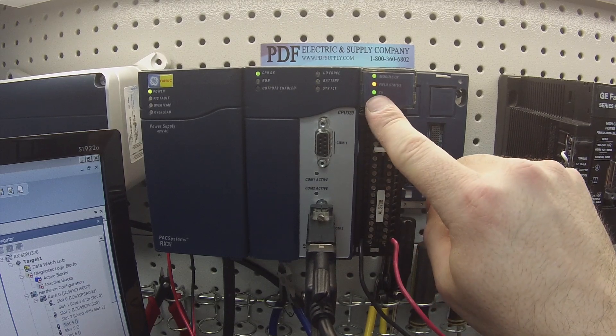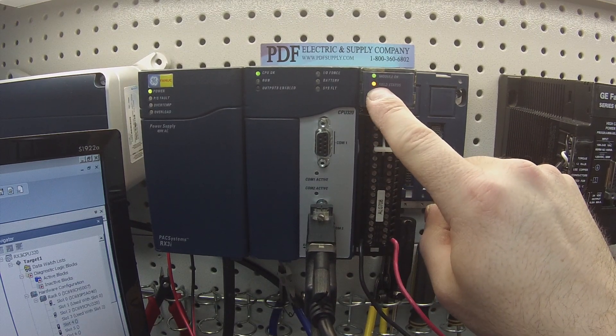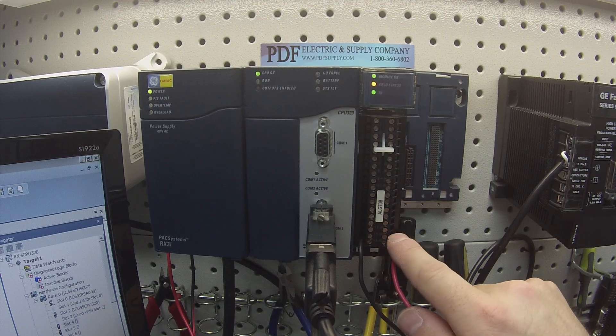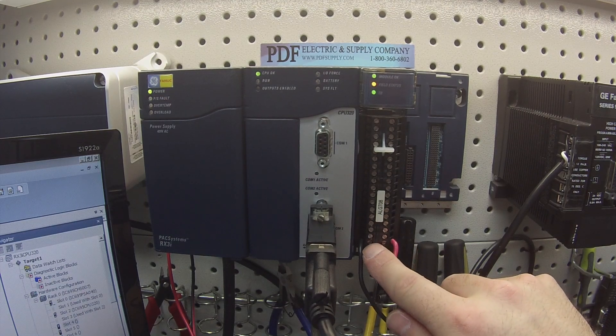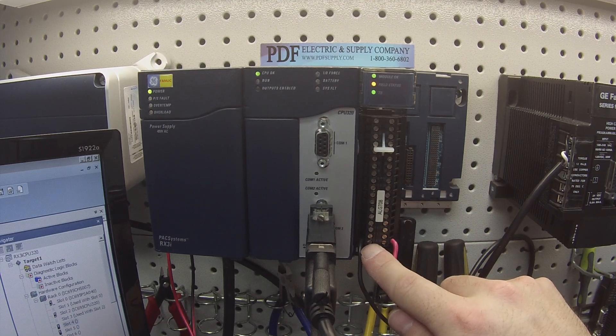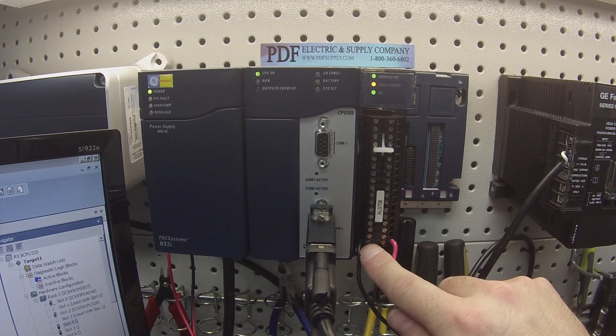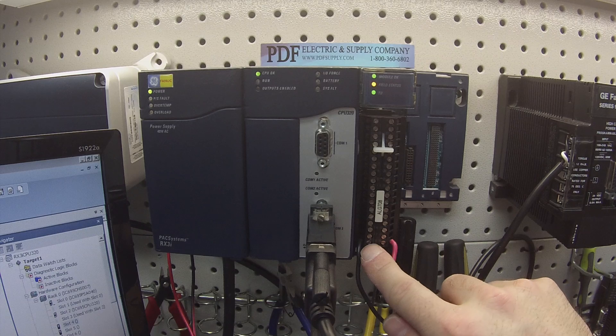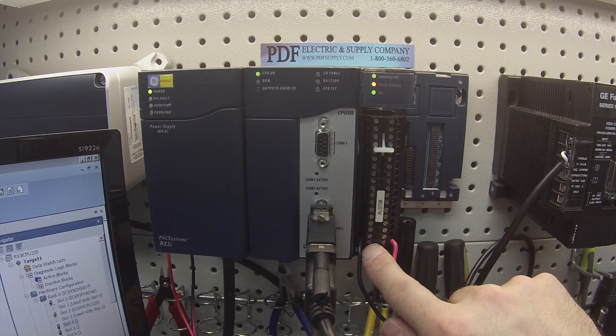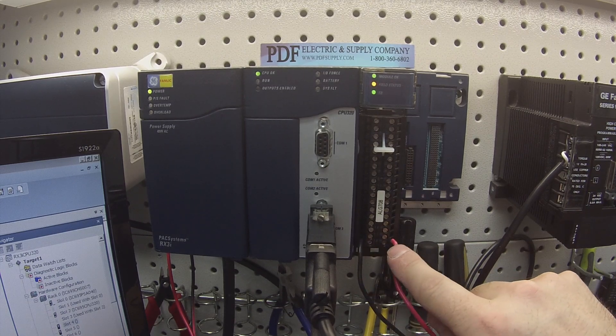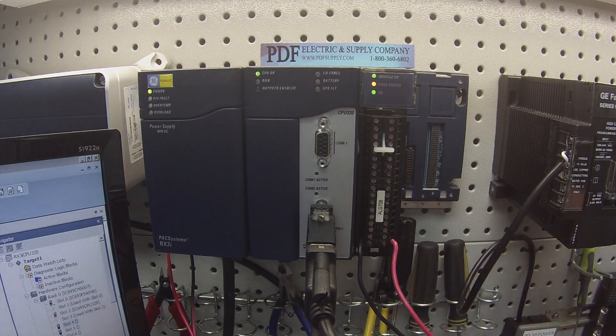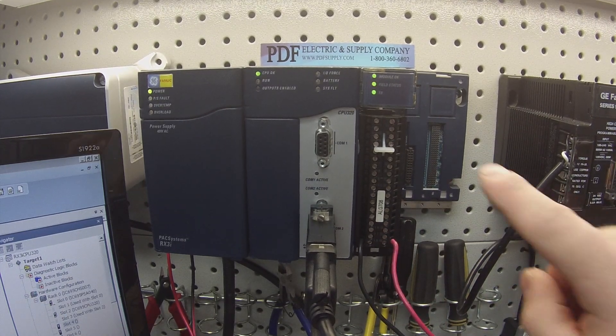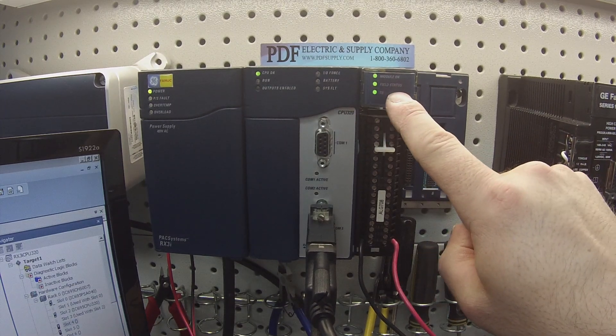It detects that the terminal block is there and our field status is related to these two wires here. This is an output that's going to require power coming in from an external source. I have a 24 volt DC power supply. My negative lead is going to the bottom left terminal which is terminal number 18 and my positive lead is going to terminal 36, bottom right. When I power that up, I should have a green light.